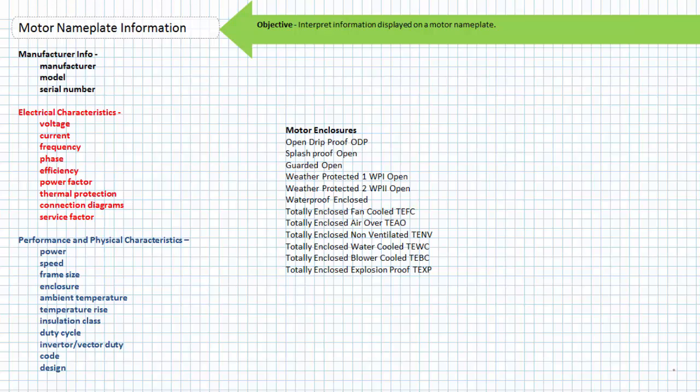While we're on the subject of enclosure, both motors that are open or fully enclosed need a means of keeping cool and sometimes include fans, heat dissipating fins, blowers, and even water coolers to do so. If you're working in a sawmill or a flour mill or some other environment that's dusty and dirty, low-level maintenance often takes the form of simply keeping things clean. Given heat degrades components, imagine working in an already hot environment wearing a quilted jacket stuffed with 3 inches of sawdust all day long. Keeping motors clean is a valid maintenance task that ensures the long life of your equipment.